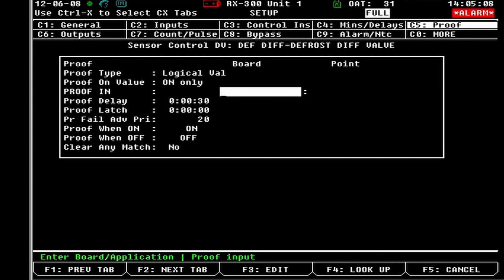So you could have a proof. Say if you're using it for something else, you could tie the proof into it, if you're needing to prove that something's on. So say you're using this for like a heater reset or a heater proof, and you want the heater to be on. If the logic's made, you want to proof it in to make sure it's actually on.